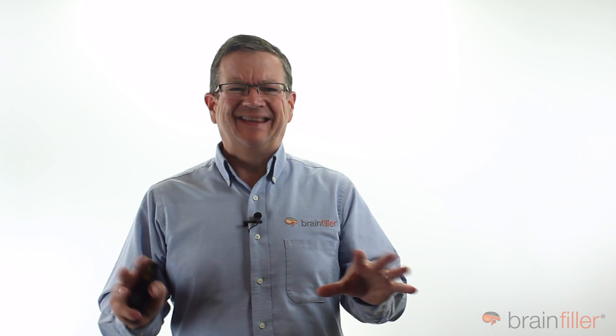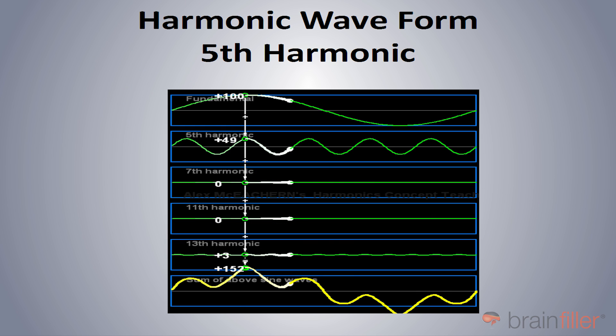The math of what harmonics are — just a multiple of a given frequency — that's easy. But what really are harmonics, and how do they get into the power system? This graph right here shows the top waveform as the 60 Hz characteristic. Just below it, I show the fifth harmonic at 49%. So if we have 100% of the 60 Hz component and 49% of a fifth harmonic component, the waveform on the very bottom shows those two waveforms superimposed on each other — the 60 Hz with the 300 Hz, or fifth harmonic, almost like a carrier wave. You have a really heavily distorted waveform.